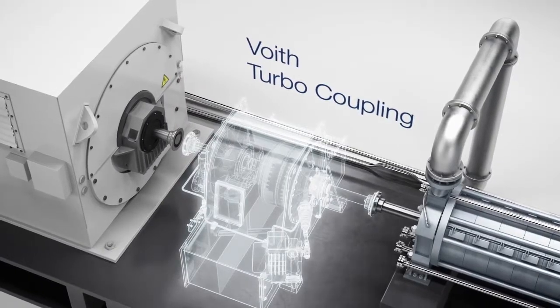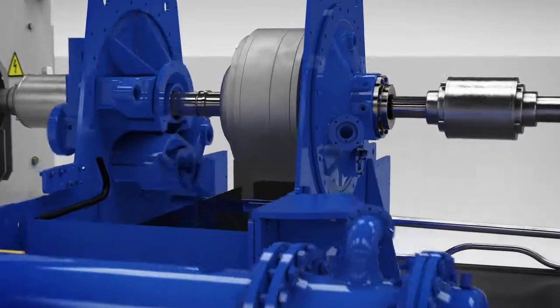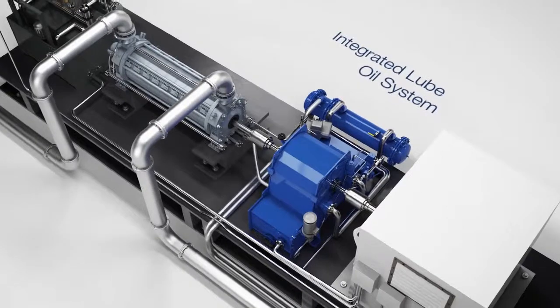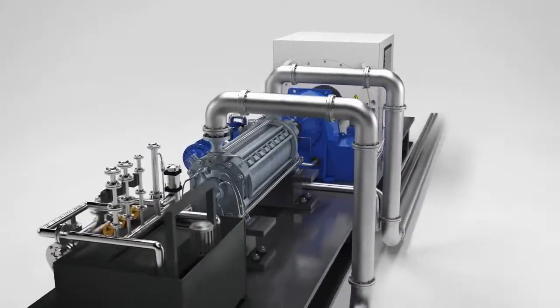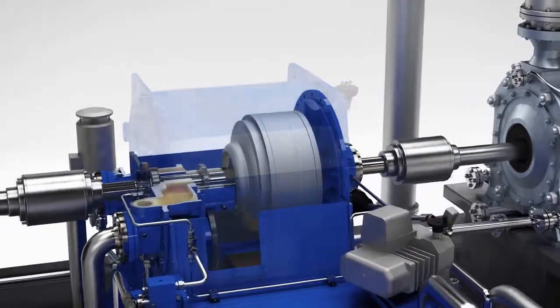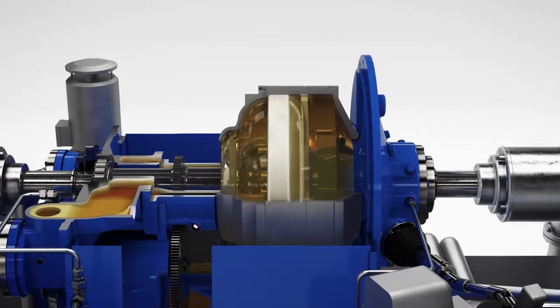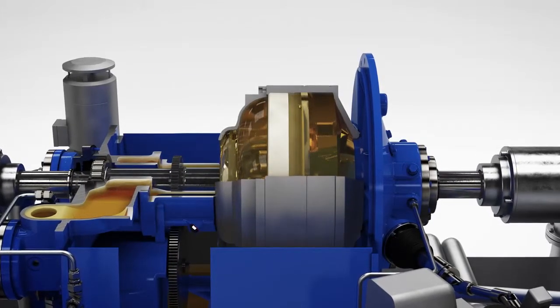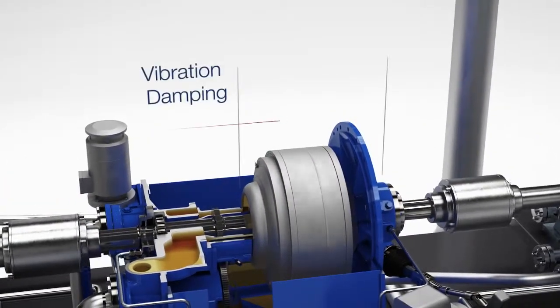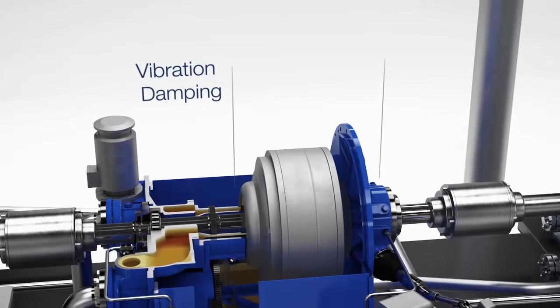Controlling pump speed using Voith hydrodynamic couplings, which feature outstanding energy savings and high reliability, is a significantly more economical solution. The hydrodynamic coupling's integrated oil system supplies the bearings of the boiler feed pump and the electric motor with lubricating oil, so a separate lube oil supply system is no longer necessary. The principle of hydrodynamics is based on using oil to transfer the power coming from the motor, with no mechanical connection between the motor and the driven machine, ensuring wear-free power transmission. At the same time, the oil serves as a damping medium, filtering out torsional vibrations and torque peaks, which increases the service life of the entire driveline.